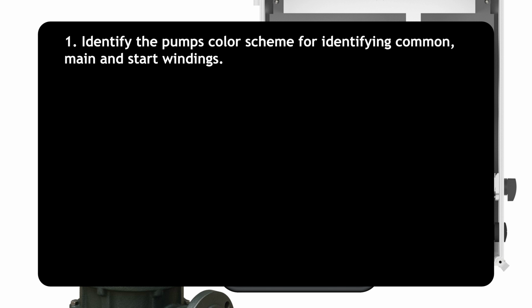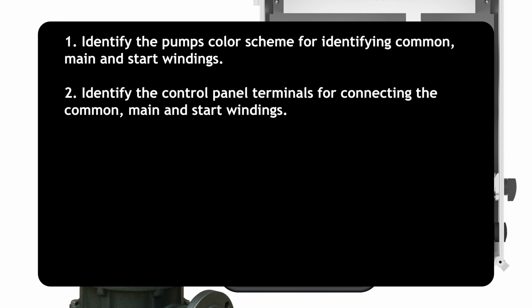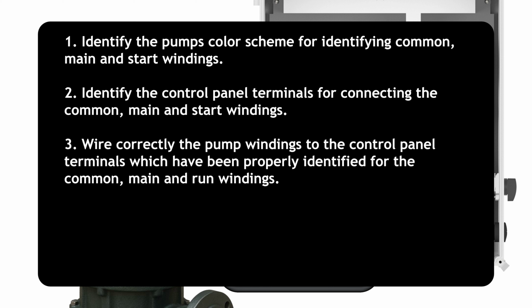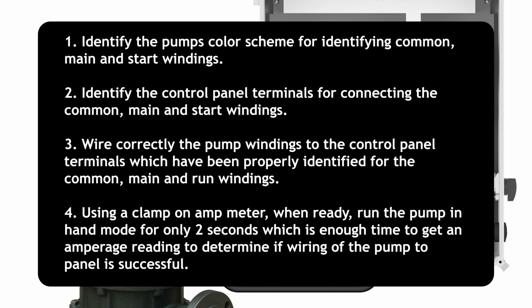1. Identify the pump's color scheme for identifying common, main, and start windings. 2. Identify the control panel terminals for connecting the common, main, and start windings. 3. Wire correctly the pump windings to the control panel terminals, which have been properly identified for the common, main, and run windings. 4.